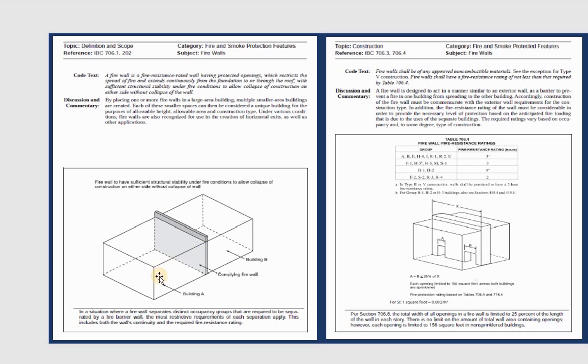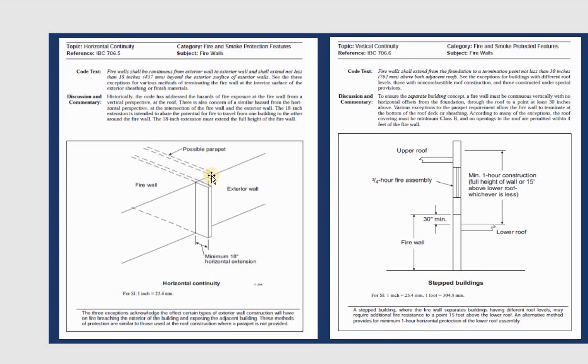For two buildings together — Building A and Building B — with different occupancy groups requiring a firewall between them, look at the top portion: it's darker and extends above the lower section. This is called the parapet — the external wall extending outside the building. It's designed to reduce fire spread from one building to another. The parapet should extend a minimum of 18 inches outside the exterior wall.